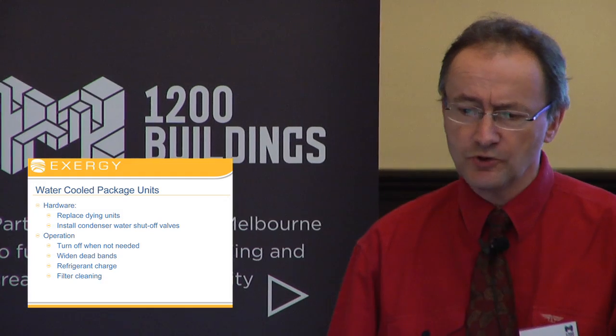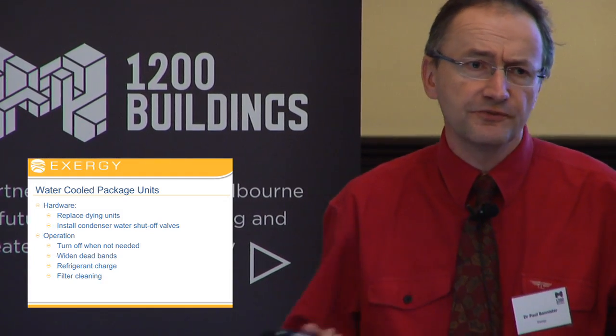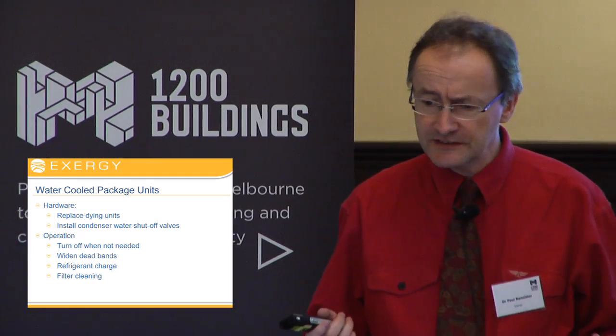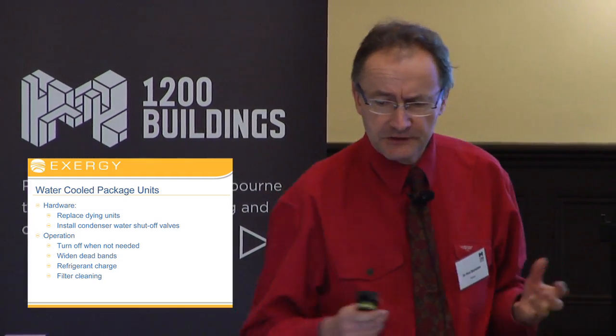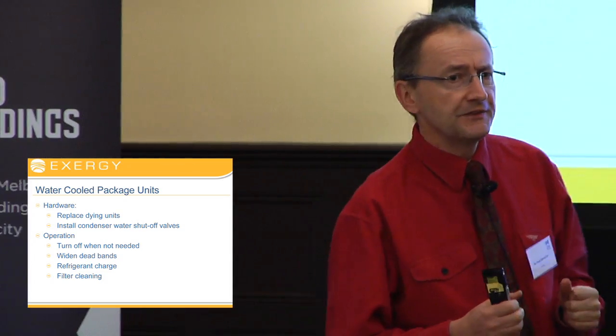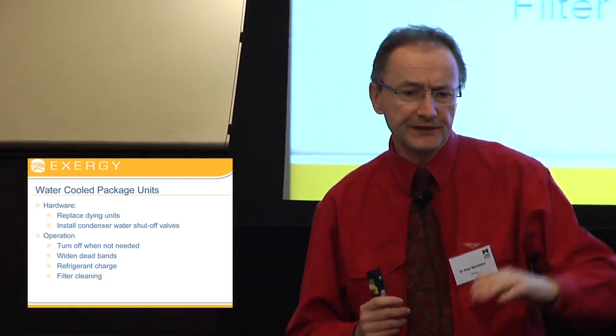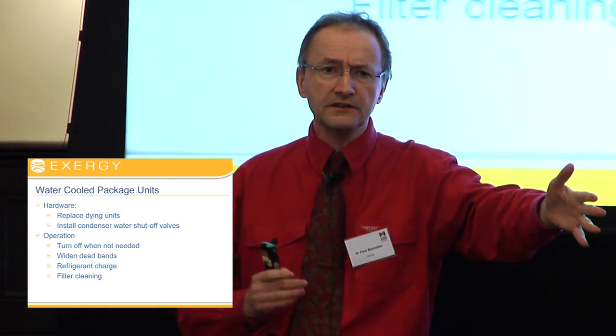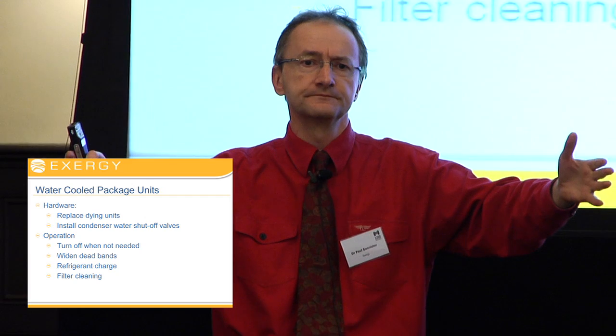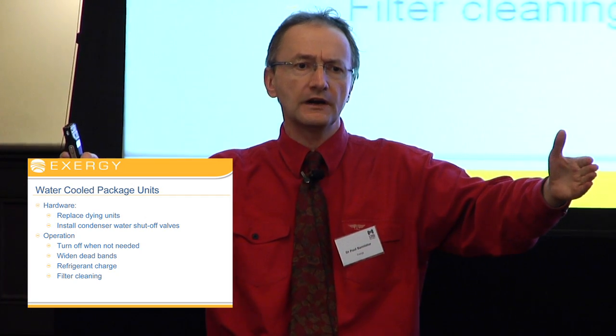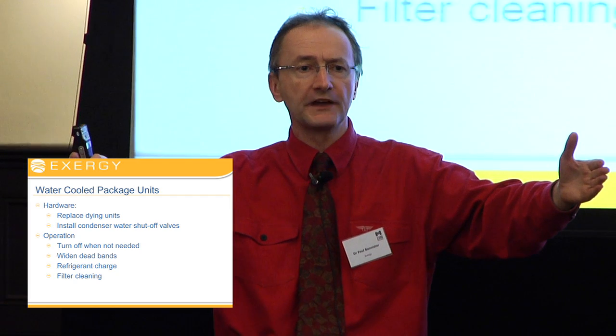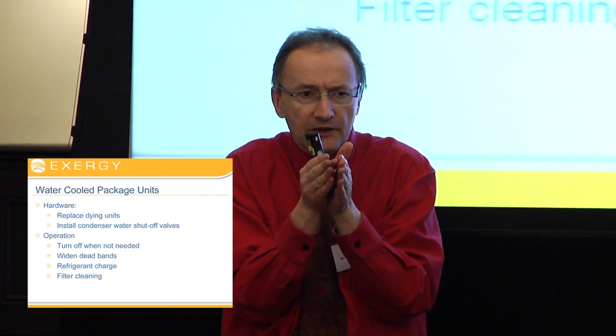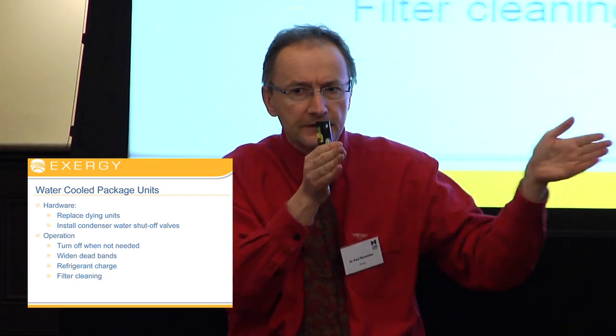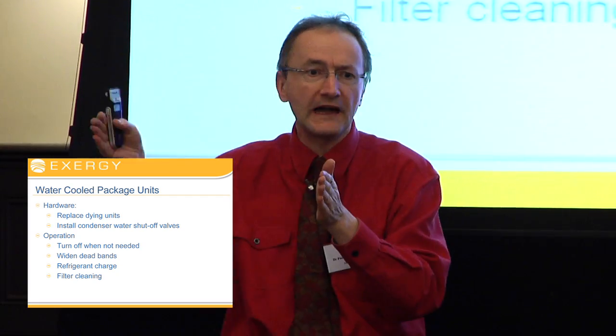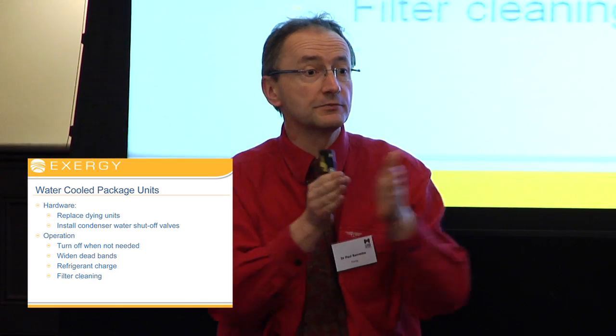Other things, well, of course, again, turn it off. Turn off your water-cooled package units if they're not needed. Widen the dead bands. What do I mean by widening a dead band? The dead band is the space between when you are heating and when you are cooling. So if you are operating with a small dead band, it means that you might go, I'm heating, I'm cooling, I'm heating, I'm cooling, I'm heating and cooling.